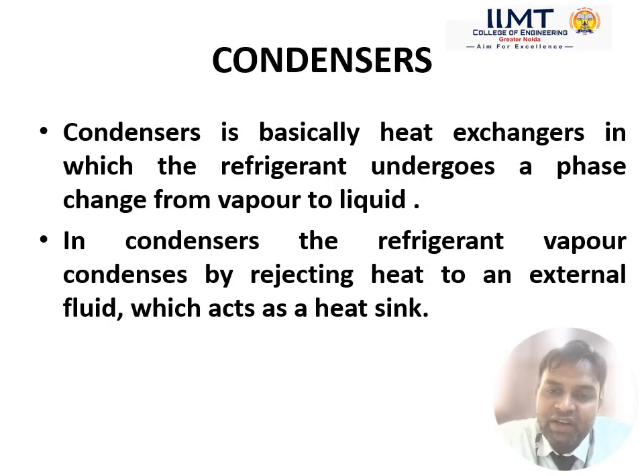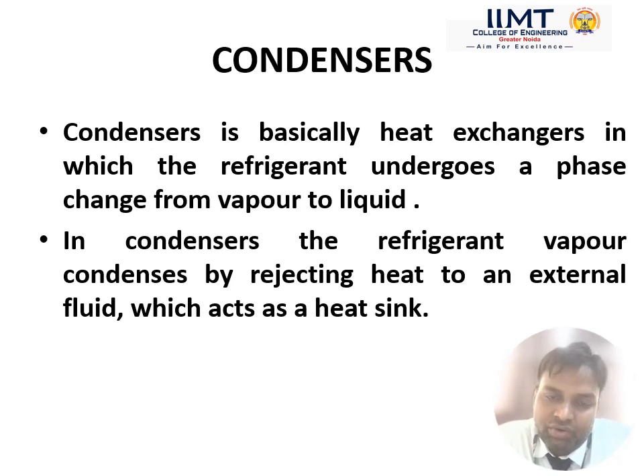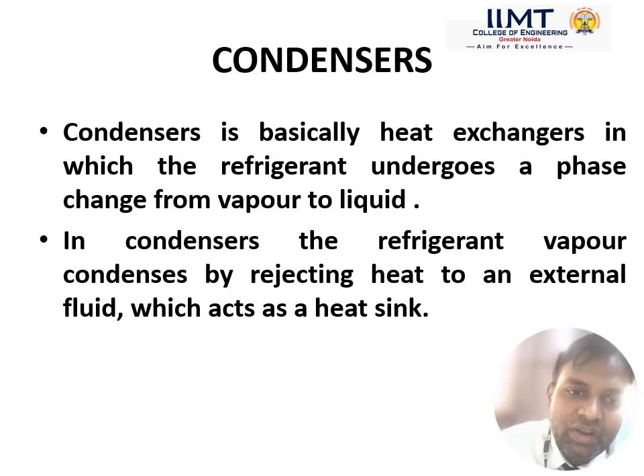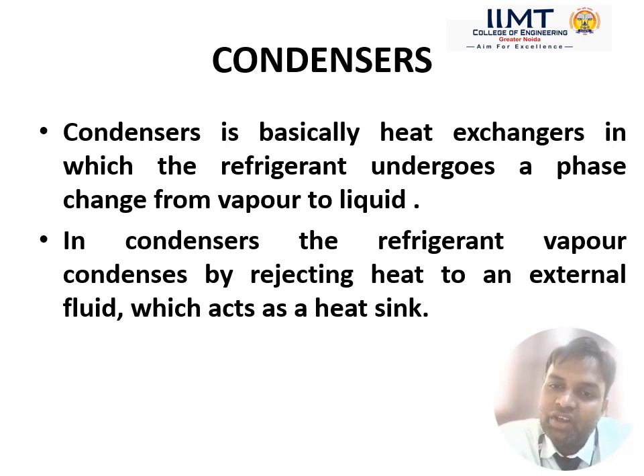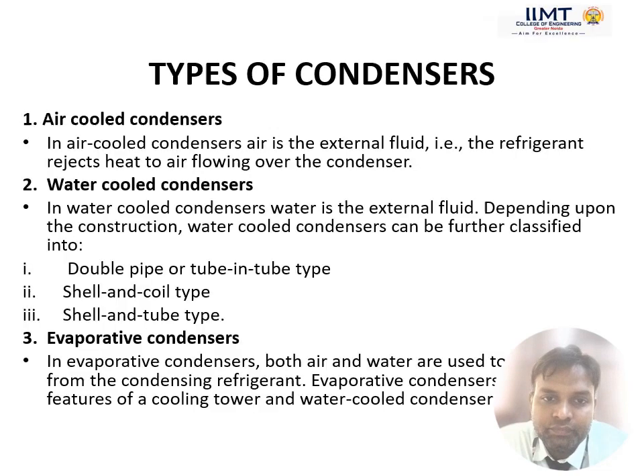The condenser is another important equipment in air conditioning and refrigeration. A condenser is basically a heat exchanger in which the refrigerant undergoes a phase change from vapor to liquid, releasing latent heat to the atmosphere. When you feel the back side of an air conditioner, the heat coming out is from the condenser — it is the heat absorbed by the refrigerant at the evaporator inside the room.